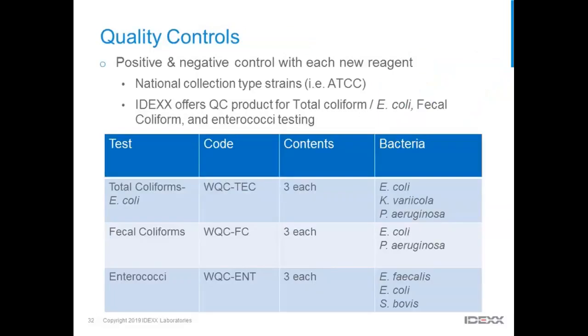On that, IDEXX does provide several QC options that can be done on our products, but we also note in our inserts that you can run positive and negative controls using bacteria obtained from culture collections such as ATCC. But once again, IDEXX does provide IDEXX QC products, and there are separate kits for each type of test.